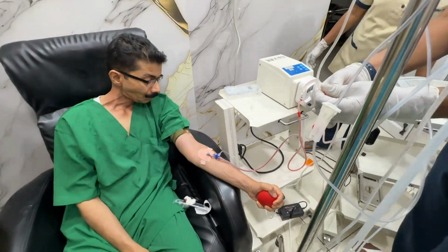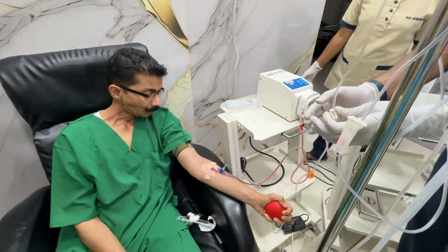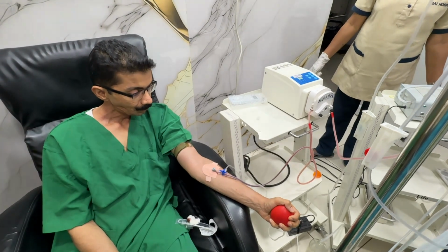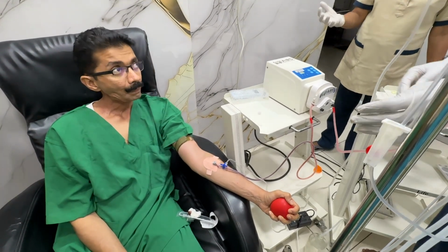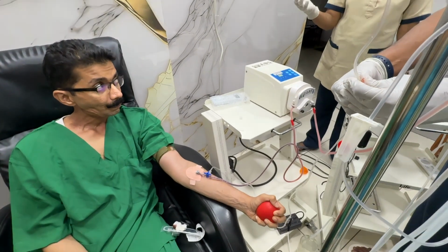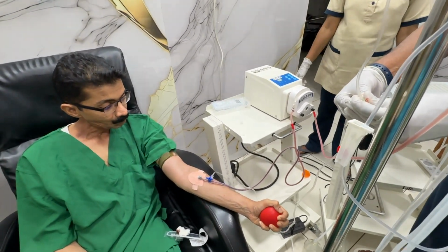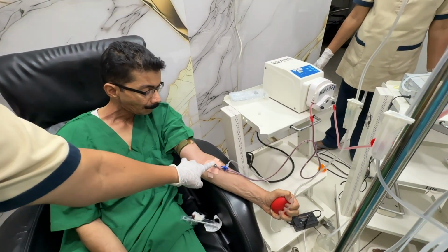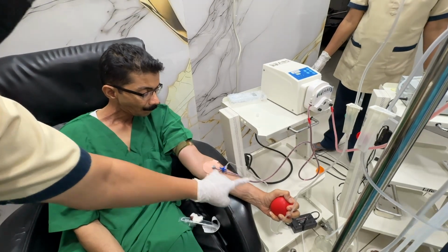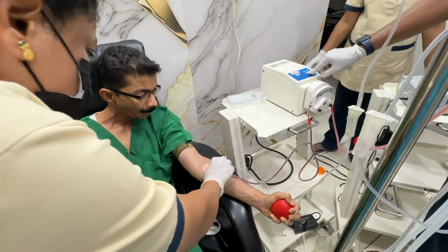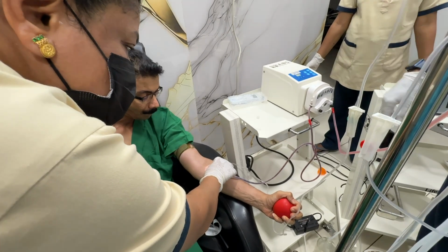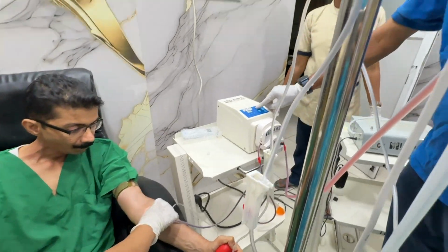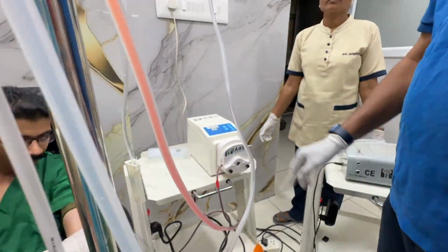In the initial stages, as the tube has heparin priming inside it, dark blood is not visible, but once the heparin flow is adjusted and the pump speed is adjusted, we can see the dark venous blood gushing out of the vein, going through the perfusion pump and rising up to the bottle.